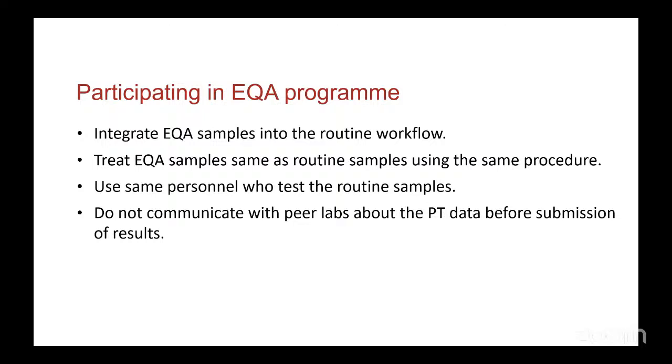Integrate the EQA program samples into your routine workflow. Let's say, for example, if it has to be registered, you can register it even from your pre-analytical and let it go on through all the processes. Treat the EQA sample as a routine sample using the same procedure. Use the same person who tests the routine samples. Anybody who is testing the patient sample is qualified to do what? To test the EQA program.